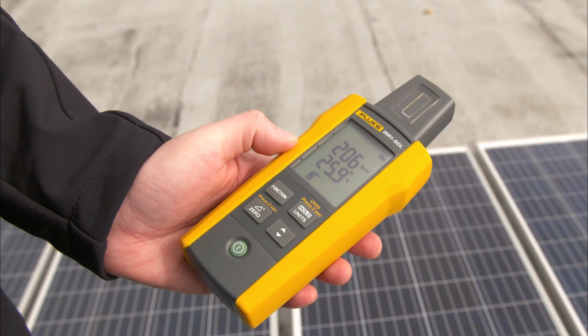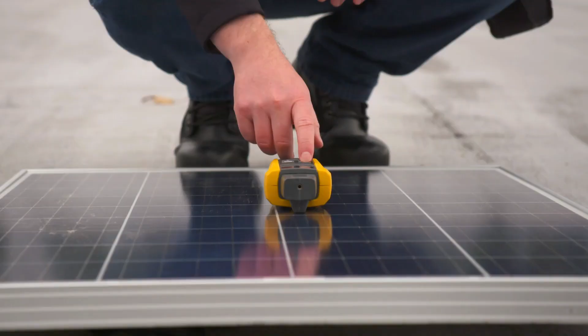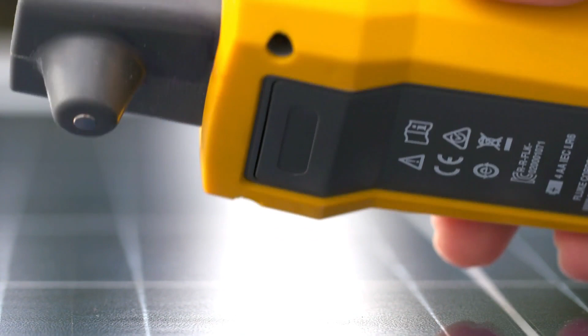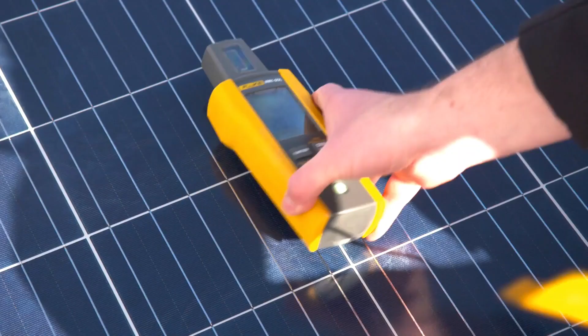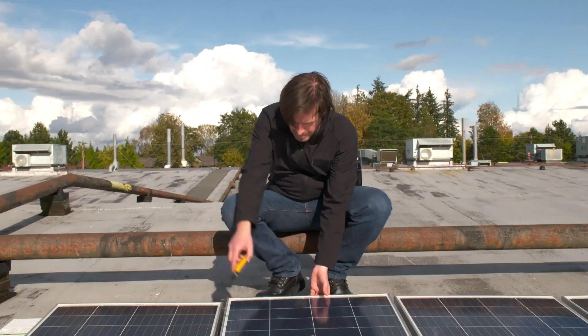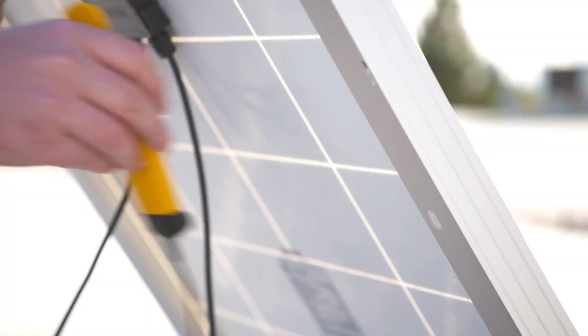With the Fluke Irradiance Meter, you can make instantaneous measurements to determine the watts per square meter solar irradiation, and measure the ambient temperature at the panel easier and faster than ever. The Fluke IRR1-SOL is the only irradiance meter that can take the temperature without needing an external probe, enabled by innovative Fluke technology that embeds an integrated conductive temperature sensor in the meter.